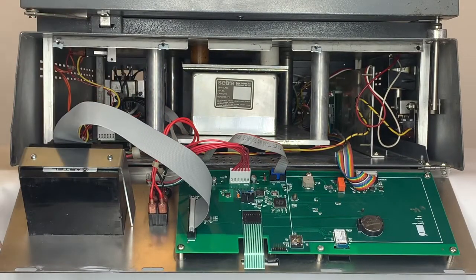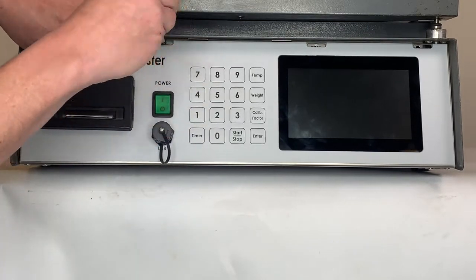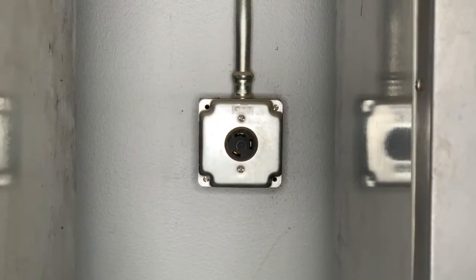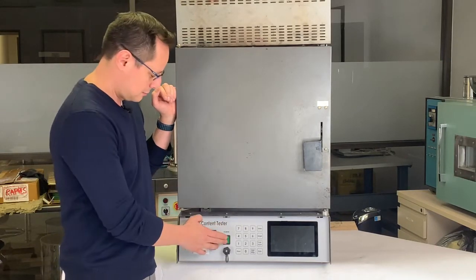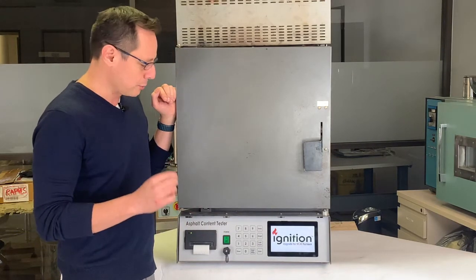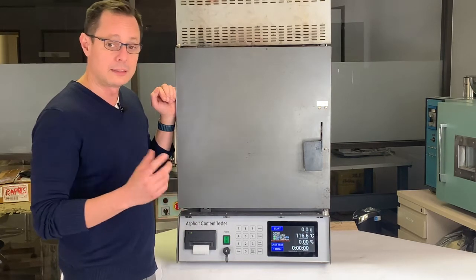Now, with the printer installed, we're going to secure the front panel to the NCAT. With everything installed, you can plug your NCAT back into the wall. Now that we've installed the front panel to the NCAT, let's turn the unit on. Please remember that you still have to calibrate your scale and also perform any routine maintenance checks on your NCAT before you start using all the new benefits and features of the InstroTek Ignition front panel upgrade.